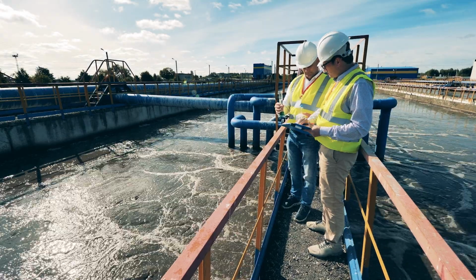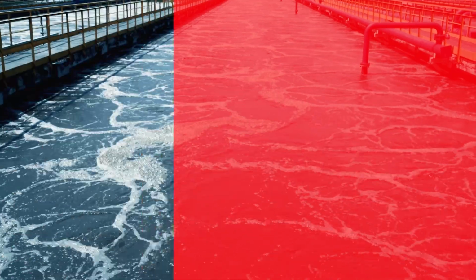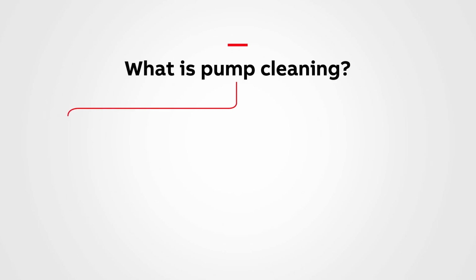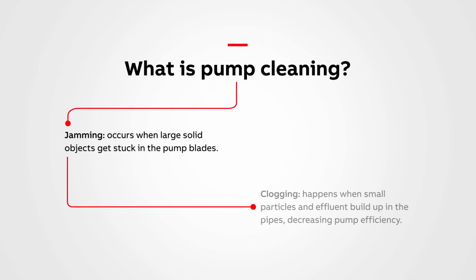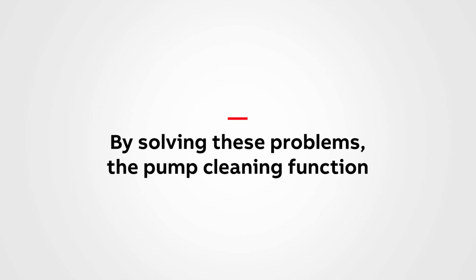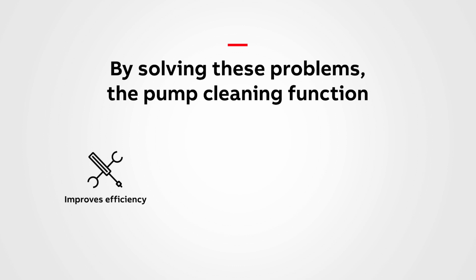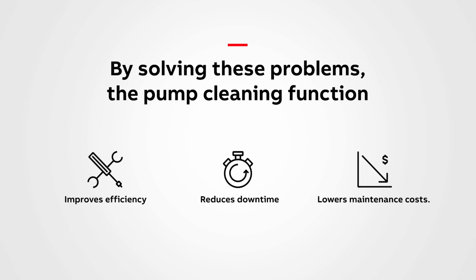What is the pump cleaning function and why do you need it for your application? This is essential in the wastewater industry, for example, in a wet well application, where jamming and clogging are common issues. Jamming occurs when large solid objects get stuck in the pump blades. Clogging happens when small particles and effluent build up in the pipes, decreasing pump efficiency. The pump cleaning function allows the pump to alternate forward and reverse directions, releasing or cutting through solid objects and flushing effluent away. By solving these problems, the pump cleaning function improves efficiency, reduces downtime, and lowers maintenance costs.